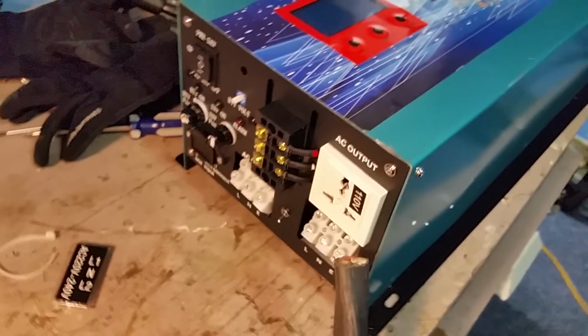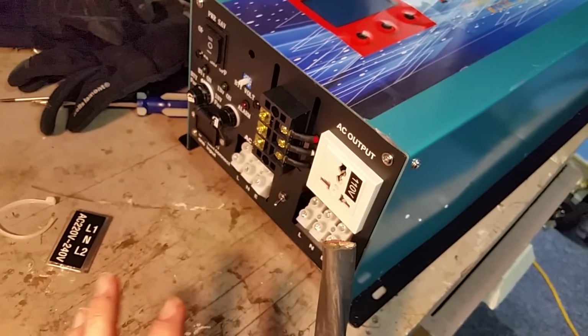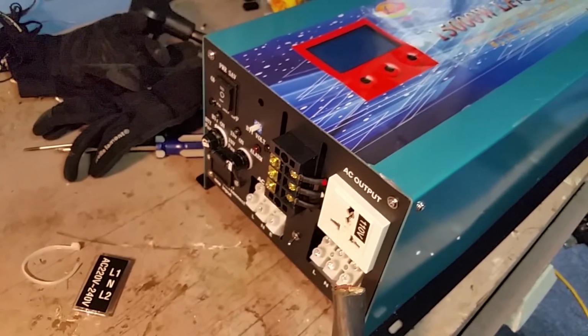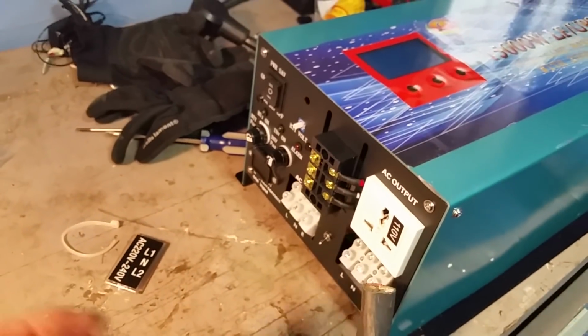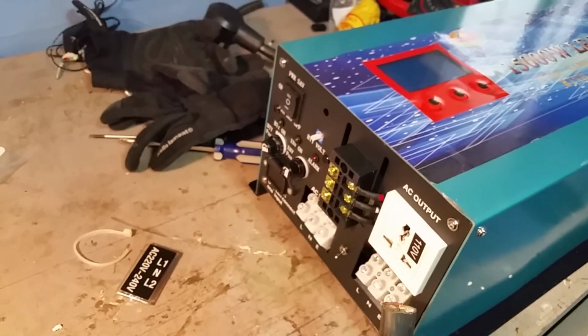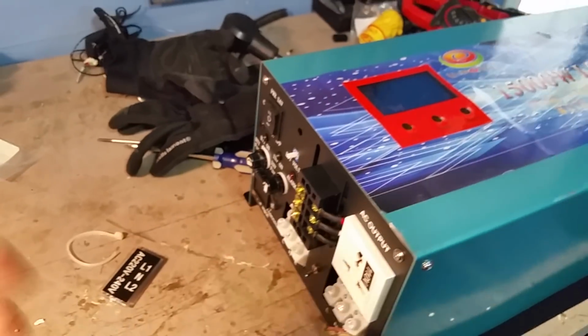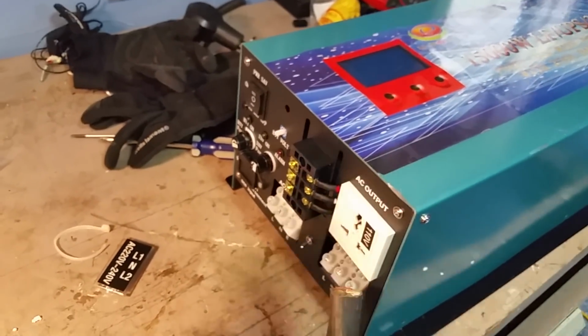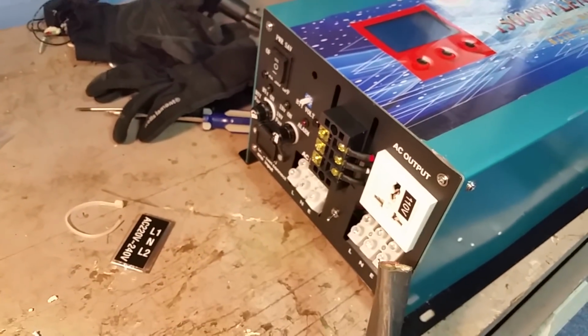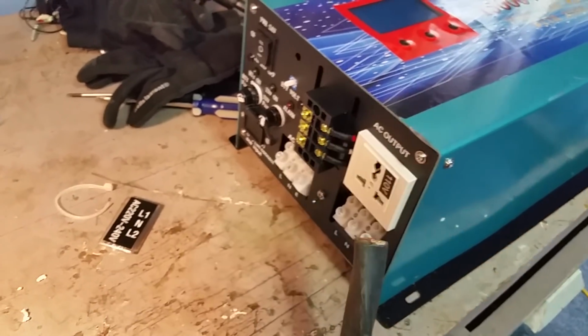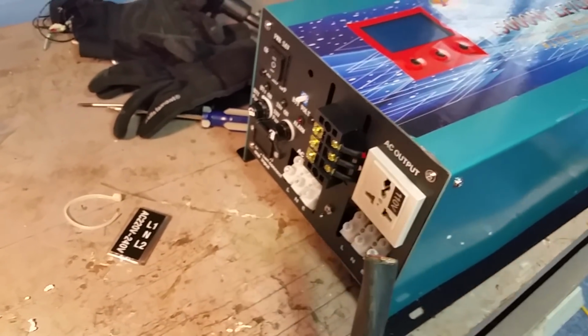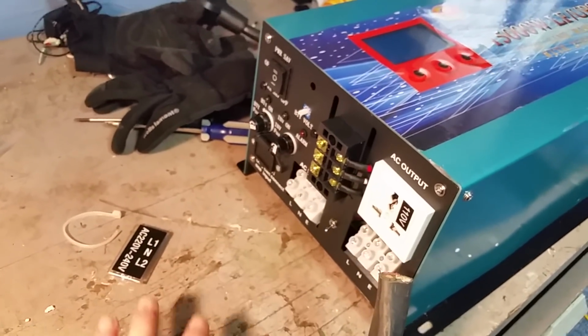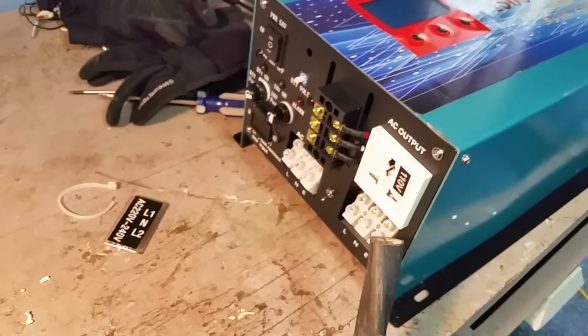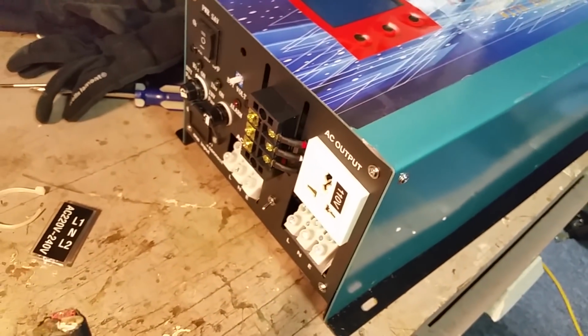My test load is power factor 1, and it's important to understand that an inductive load like a vacuum cleaner, a dehumidifier, or an air conditioner with a compressor are not power factor balanced devices - they might have a power factor of 0.1 or 0.5. So that's something to keep in mind when calculating continuous loads. Same thing with startup loads - those inductors surge a lot of current to get started. But my test load has none of that. It has a very gentle ramp up, and I can control the number of amps. I'll show you on a couple different amp meters once I hook it up outside.